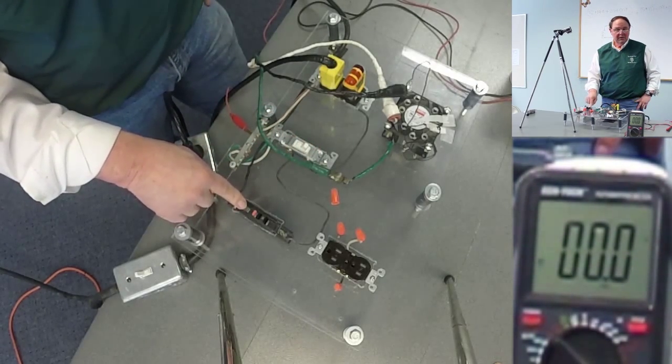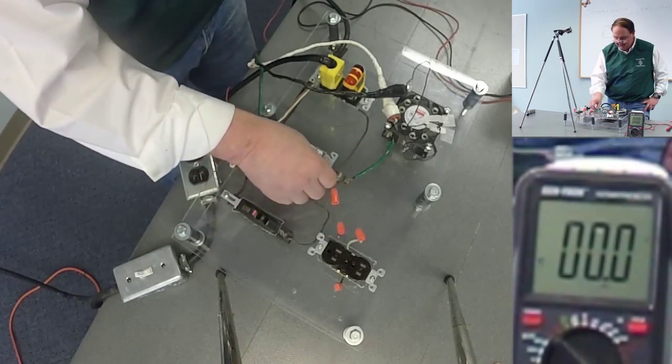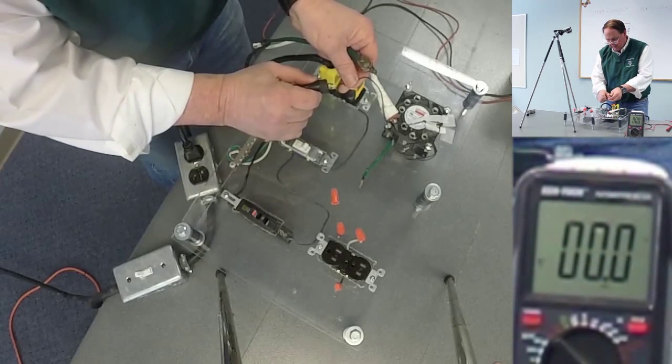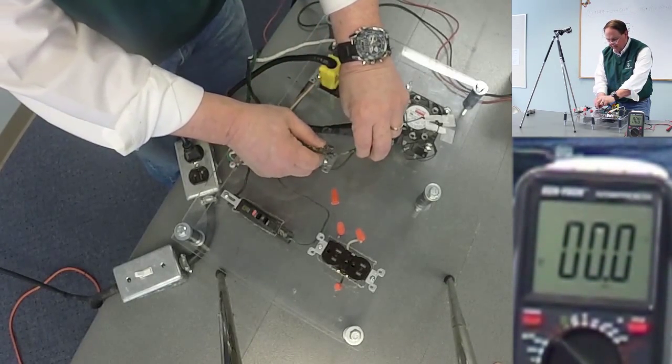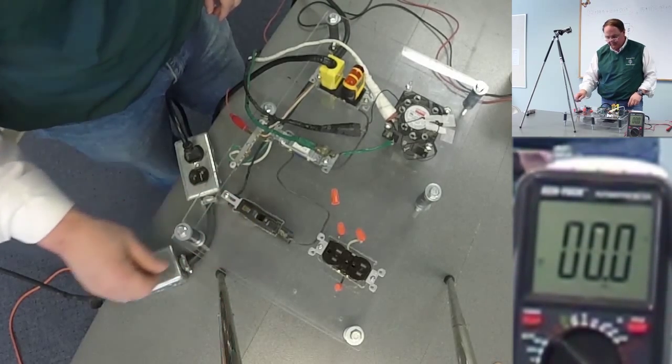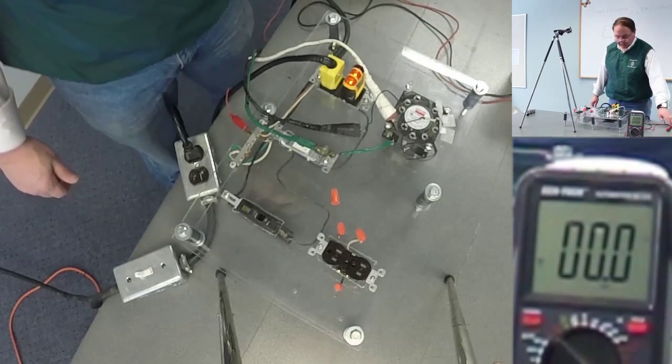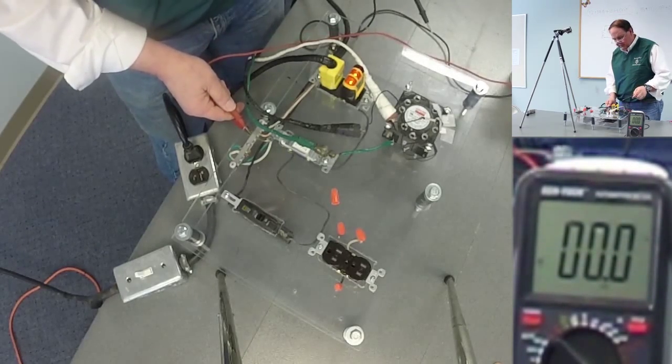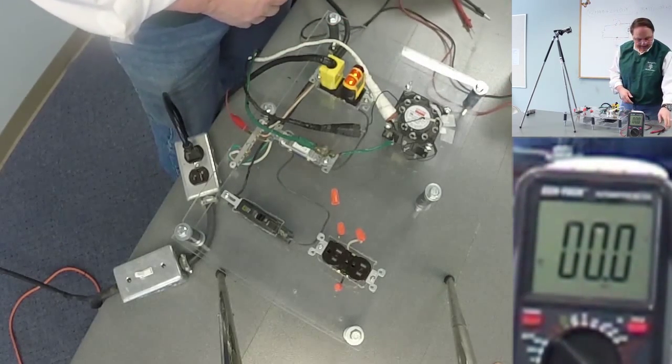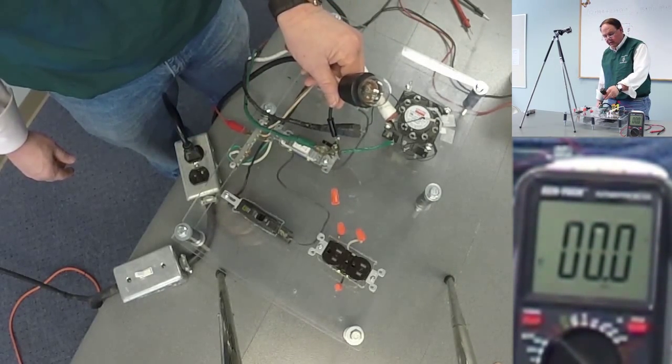We're in good shape. Let's fix this in the right manner now. We'll take this off and see if we're working correctly. We reset our breaker, our overcurrent protection device. As you can see, the fan's rolling, everything's fine again. We'll check it. Let's make sure we don't have any voltage. As you can see, there's zero voltage showing up right here, as should be. We take our light test, which everyone likes to see.